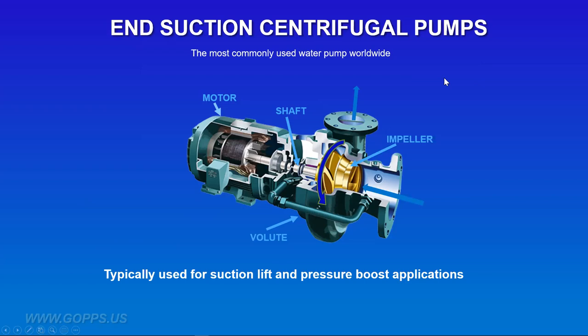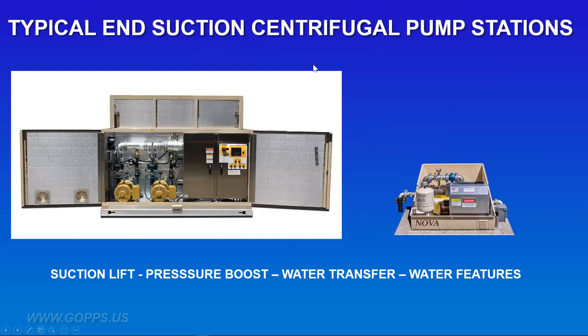The most common pump in the world is the end-suction centrifugal pump. The impeller is located inside the volute so that water and pressure are contained. There's the motor and there's the shaft. The impeller spins, forces water outward, which draws water inward. One important thing to note: the pump — the water end — and the motor are two entirely separate things, made by separate manufacturers. Pump manufacturers design the pump end, then find a motor from another manufacturer to mate with their pump via the shaft to energize it. End-suction centrifugal pumps are typically used for suction lift applications and pressure boost applications.